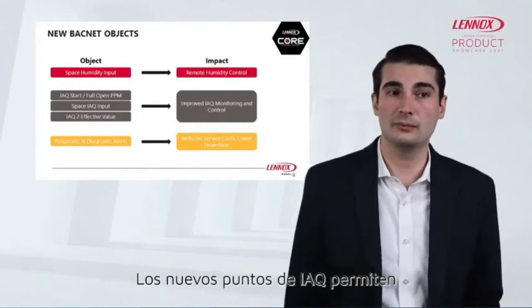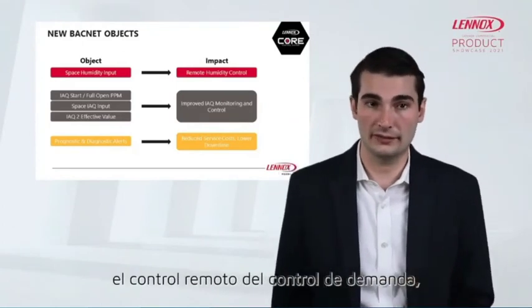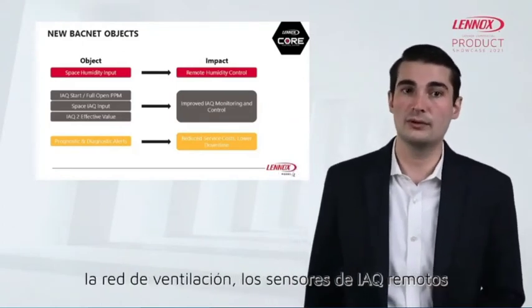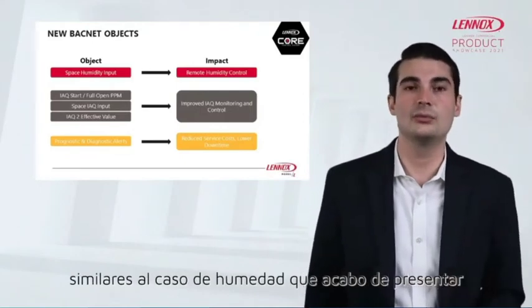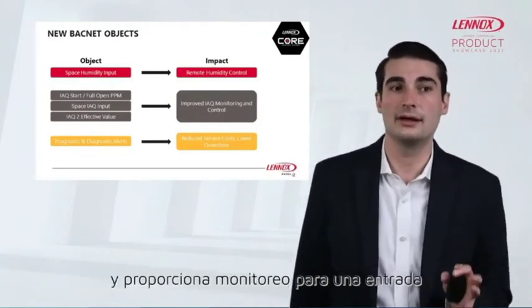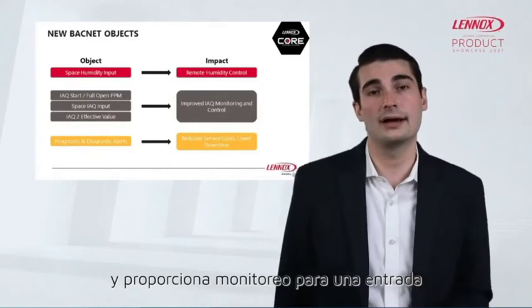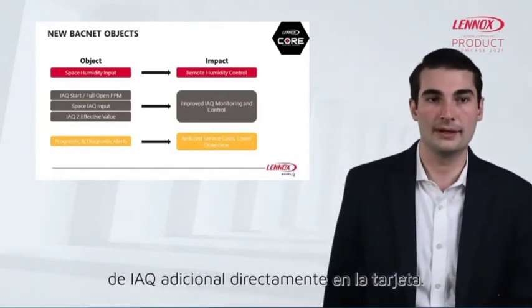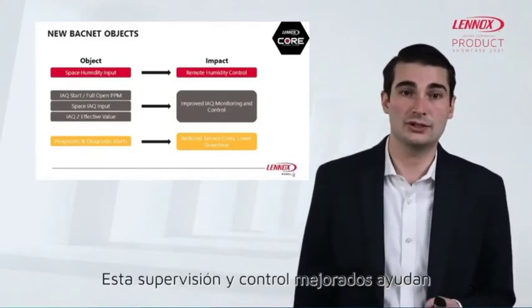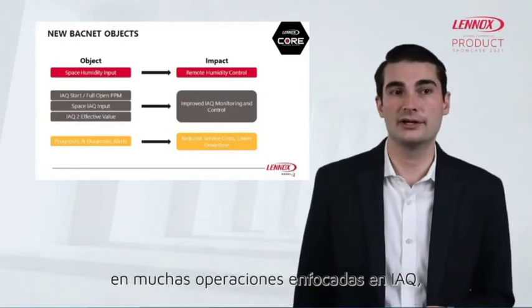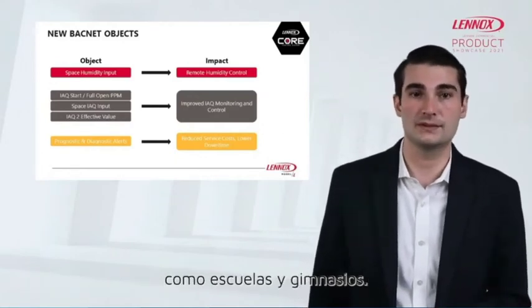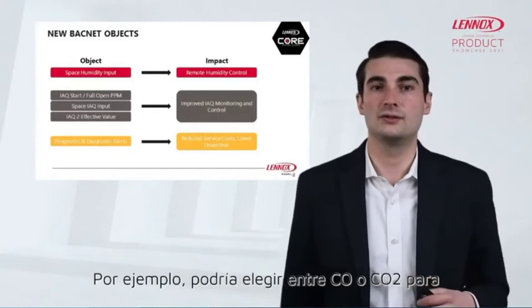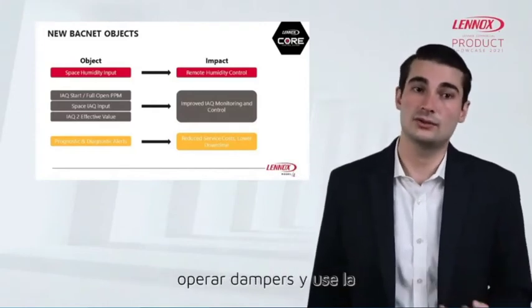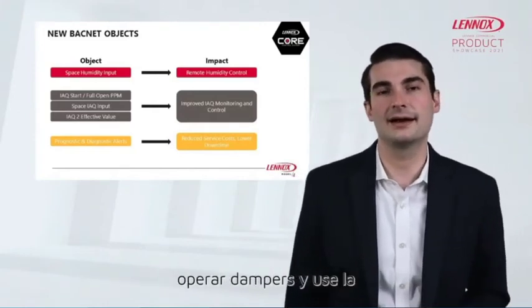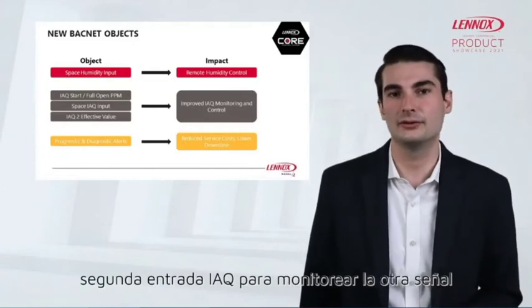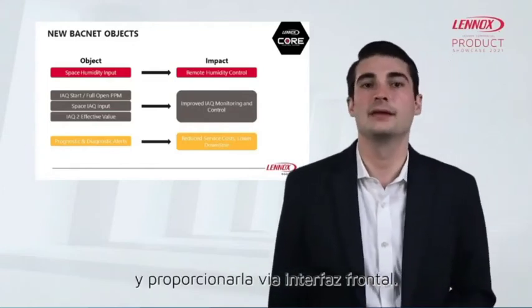The new IAQ points allow remote control of demand control ventilation. Network remote IAQ sensors, similar to the humidity case that I just laid out before, and provides monitoring for an additional IAQ input directly on the board. This improved monitoring and control should help in many IAQ-focused operations, such as schools and gyms. For example, I could choose either CO or CO2 to drive damper operation and use the second IAQ input to monitor the other signal and provide that through the front end.